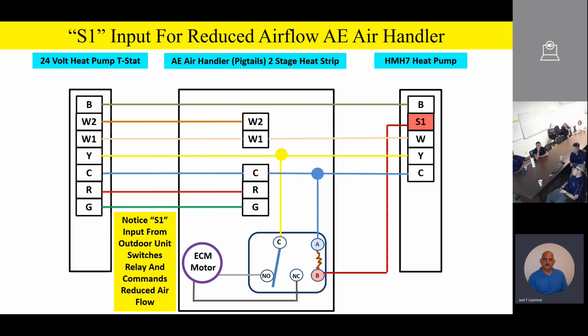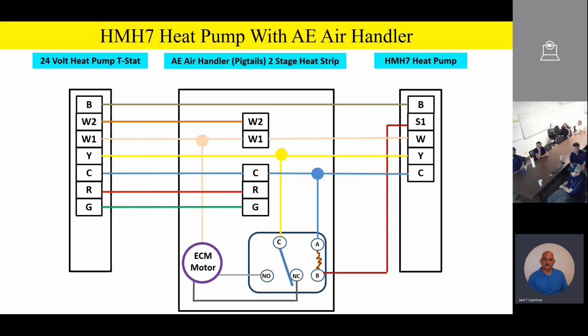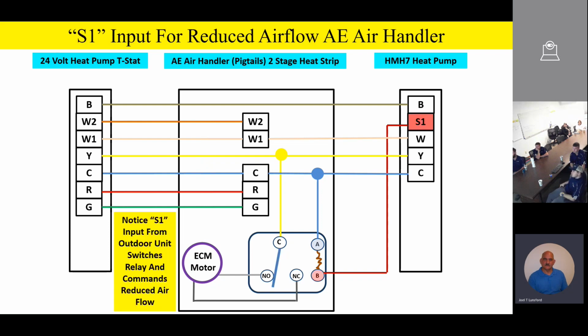So let me go back real quick. There's 100% airflow right there. And then when we animate and we switch that relay, click, we're energizing that S1 terminal, and we're going to energize the relay. We're going to switch that relay, and we're now going to command reduced airflow on the ECM motor. Does this make sense to everybody? Any questions or comments on how we're reducing airflow with that relay on the ECM motors when we hit about 60% capacity outside?